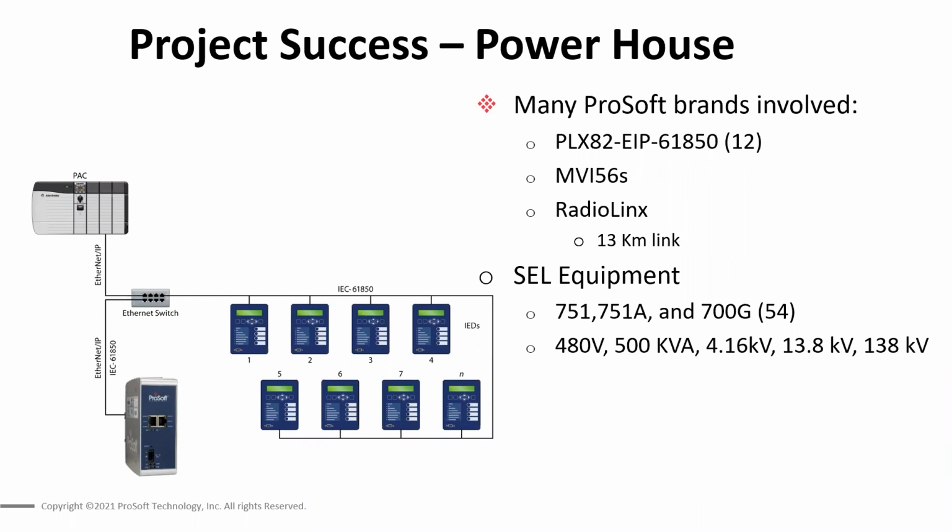Does the new module require an L8 processor? It does require an L8 processor, that is correct. The MVI56E-61850C, because of the large number of IO connections and the fast communication over the backplane, really needed an L8 processor to be able to take advantage of the double data rate over the backplane.